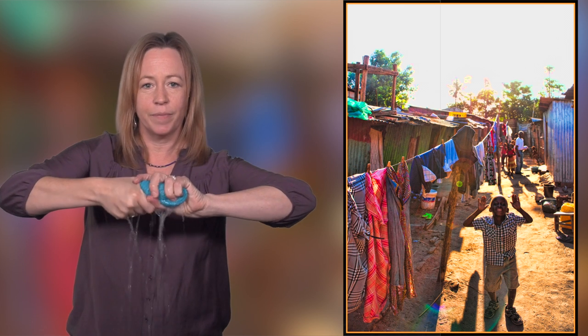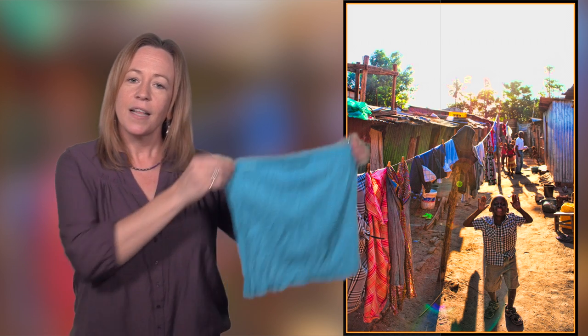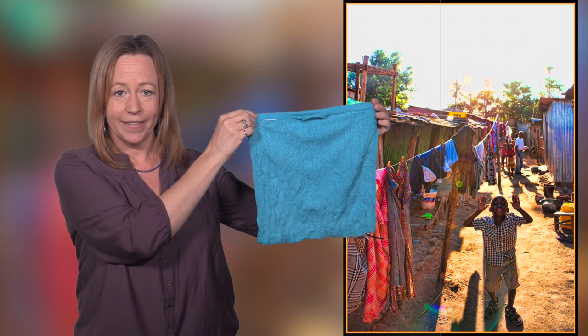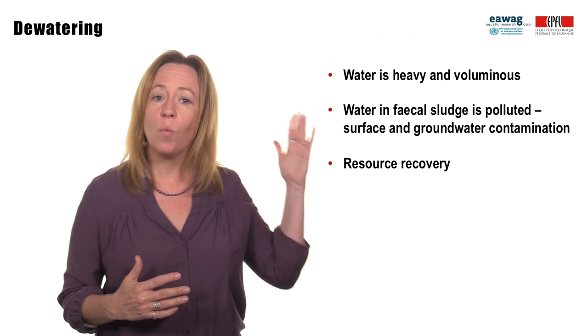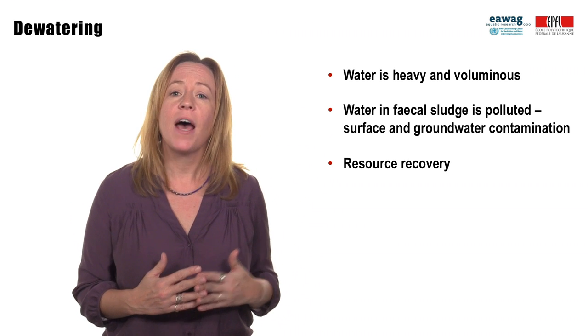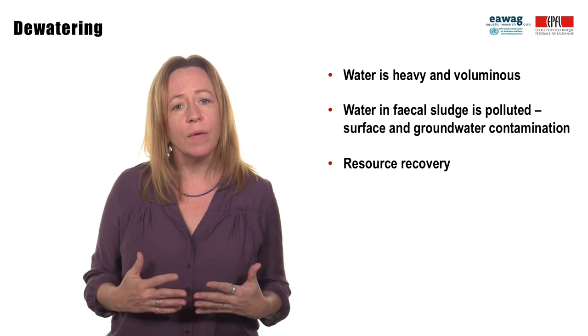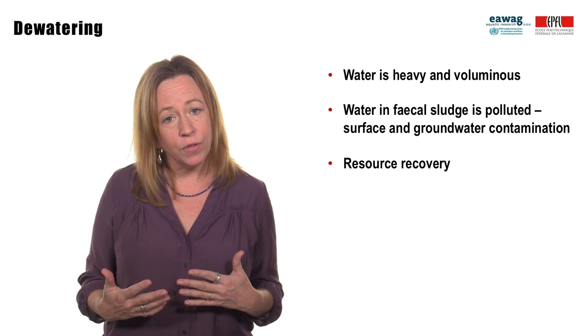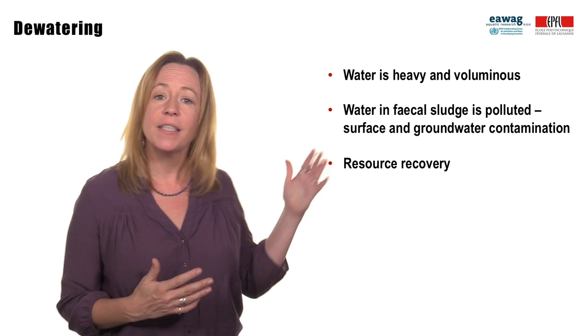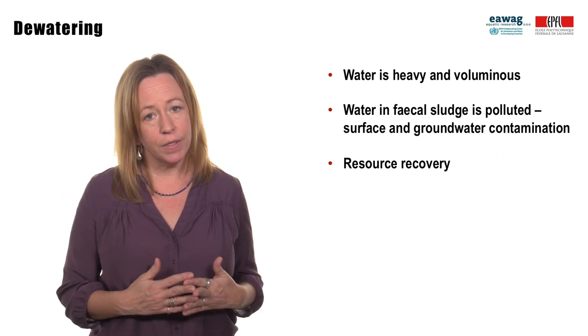The first one is dewatering. Fecal sludge is typically over 90% water, so dewatering to separate the liquid and solids is very important. Dewatering is the removal of more easily separated water, like wringing out a dripping wet towel, whereas drying is the further removal of water that is bound with the solids, like then hanging the towel on a laundry line. Dewatering is important because water is heavy and expensive to transport. Prior to effluent discharge into the environment, solids and liquids need to be separated to ensure adequate treatment can take place for public and environmental health, and dewatering is typically required for resource recovery.